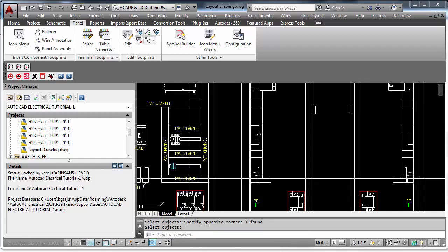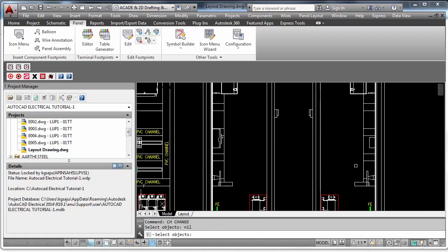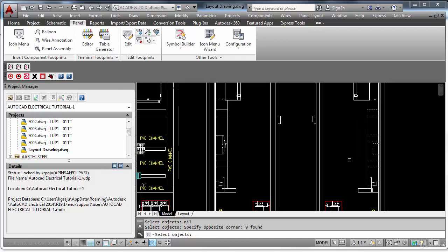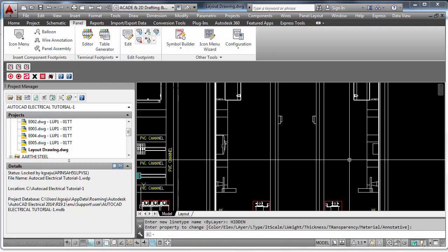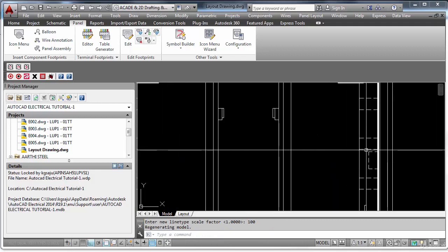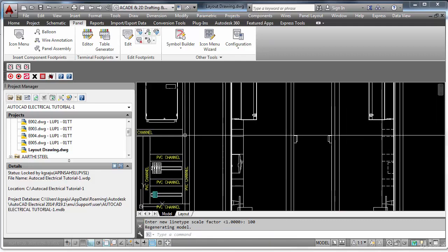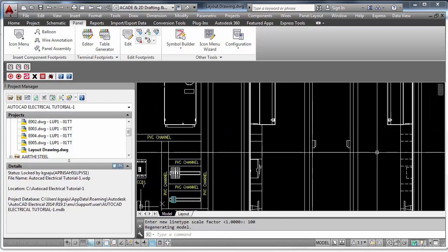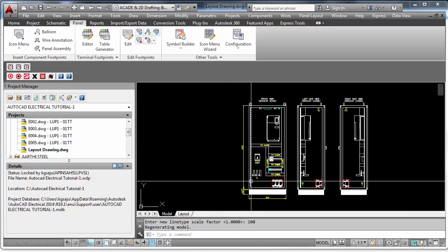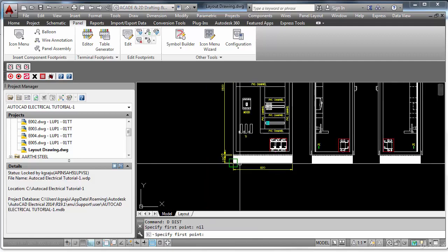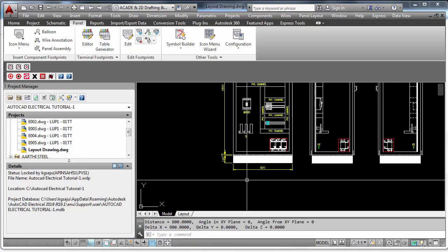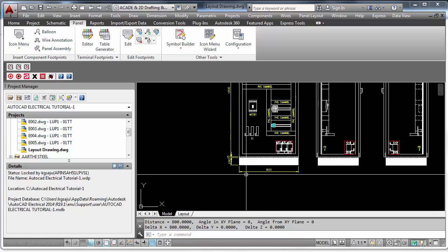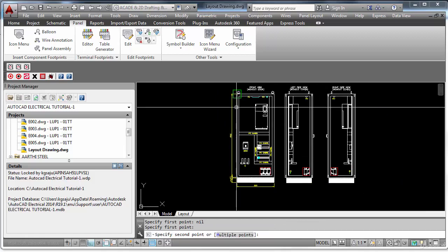This is approximately 50 mm, I know. I'll draw two lines. So this is my MCB side view. Similarly, terminals also, you can make the side view. If it is not viewing from here, what you have to do is, this is a standard: if you cannot view directly, you have to make those lines hidden lines, dashed lines. That means you are not viewing it directly, because here you see the duct is going through vertically, so you cannot see the horizontal channels directly. That's why I made it like this.